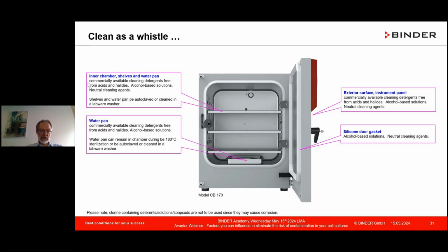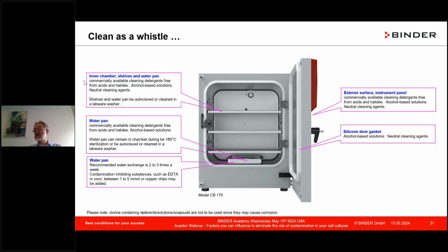Water pan, same issue, all right? Also works very, very nicely in a lab washer, or if you enjoy the 180 degrees C sterilization, you can keep the shelves and the water pan inside during that treatment. And then it's clean as a whistle at 37 degrees C, ready to load after 11 hours. And many of the incubators also have a countdown when you're working with a 180 sterilization. Recommended. A lot of questions.